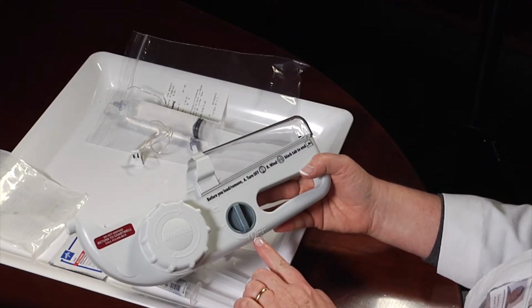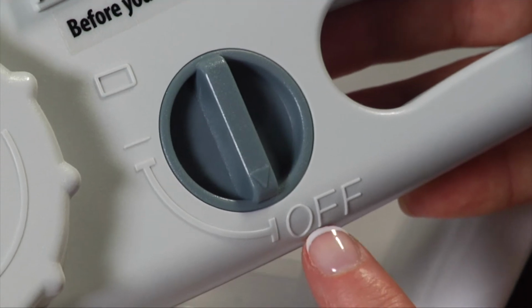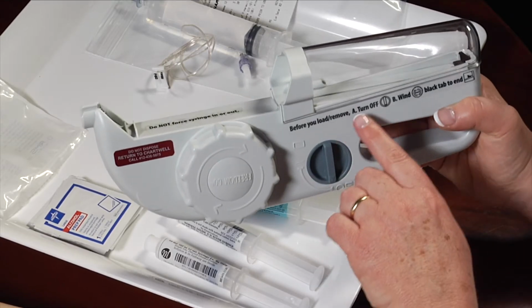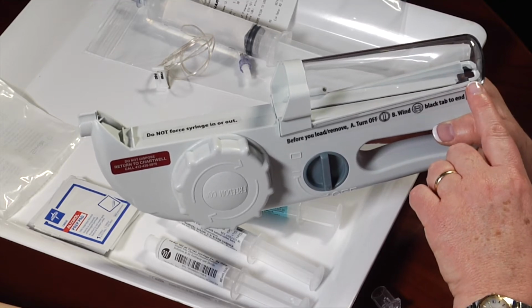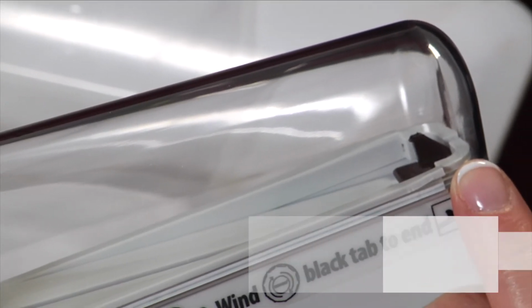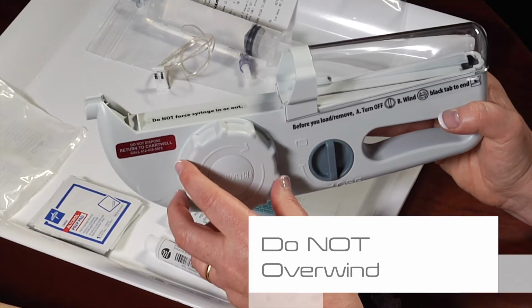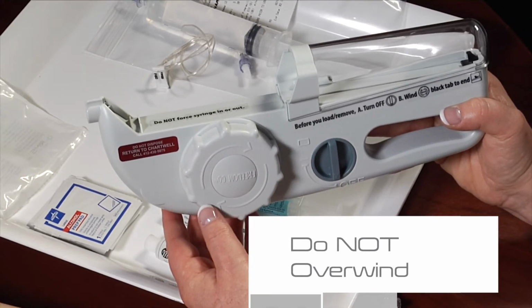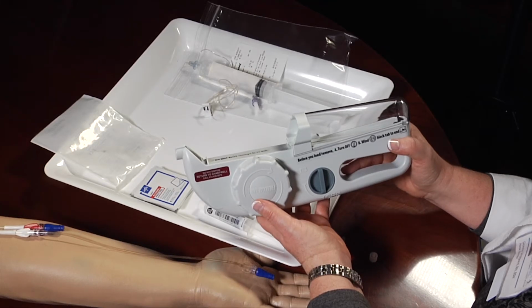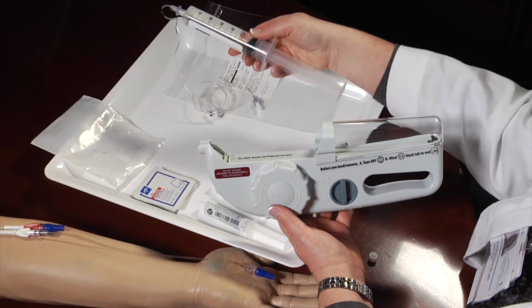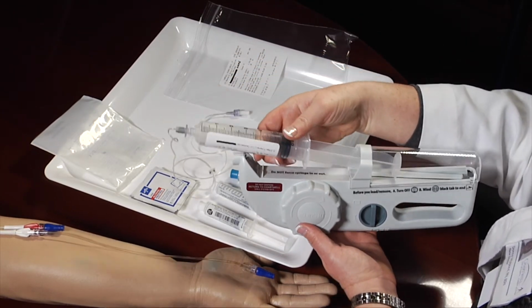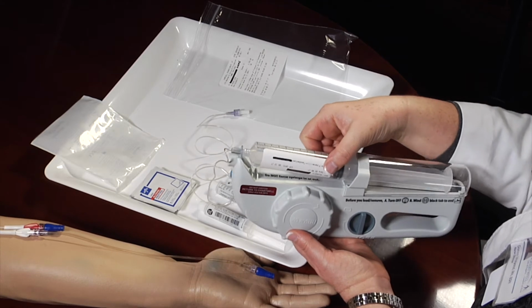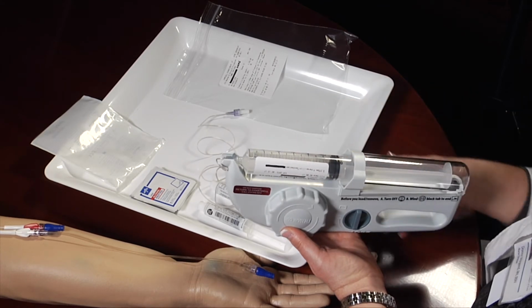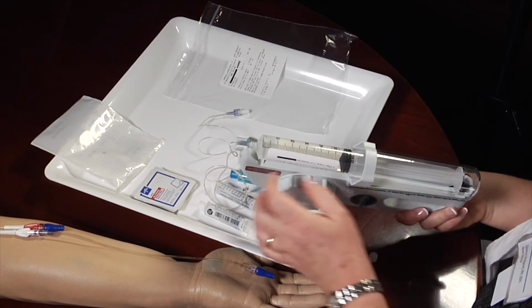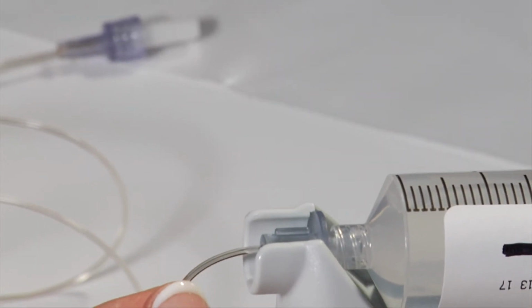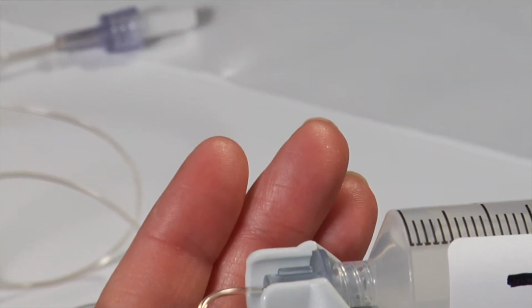Ensure the Freedom pump's on-off switch is in the off position, and the black tab in the syringe shield is at the end of its track. To move the black tab to the end of the track, wind the large knob clockwise. Do not overwind. Insert the syringe with tubing attached, plunger end first into the clear cover on the pump. Keep the syringe graduations facing up. Make sure the luer disc of tubing is fully seated in the pump's nose.